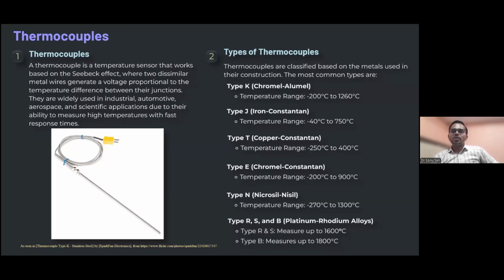Thermocouples are classified into many categories, based on the materials used for construction. For example, type K uses Chromel-Alumel and has a range from minus 200 degrees Celsius to 1260 degrees Celsius. Type J uses iron-constantan, with a range from minus 40 degrees Celsius to 750 degrees Celsius. In the same manner, there are type T, type E, type N, and type R as well as type B.